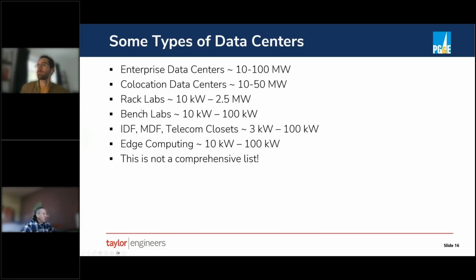And then you get into smaller, specialty spaces. We worked on rack labs where the computers themselves are being experimented on and tested, and it's a very different setting than these. We're going to have some pictures and get into more details on all of these. Bench labs, IDF, MDF, telecom closets. So this might be just a small room in a big office building, maybe one on every floor. That's the telecom closet. That's considered a data center, at least by Title 24 in California. Edge computing is a growing area. These are basically smaller distributed versions of things like the enterprise data center, but can be really small, even less than 10 kW. And there are other types out there.